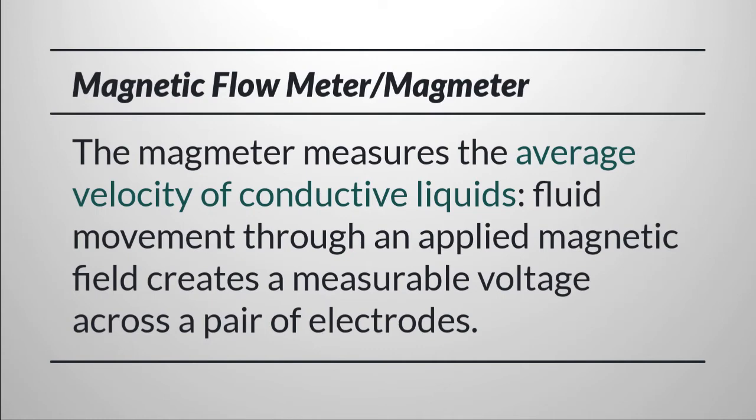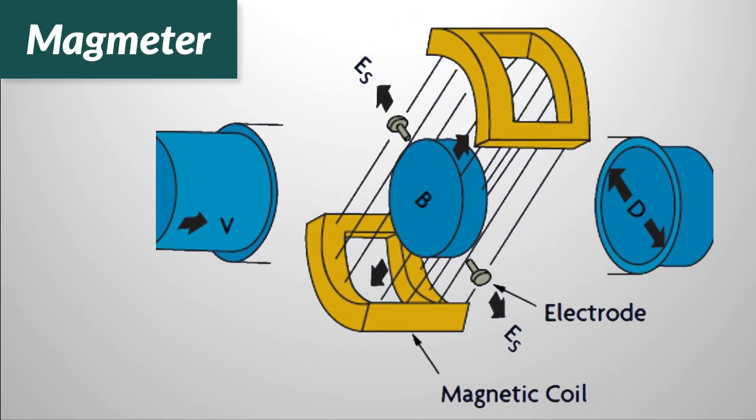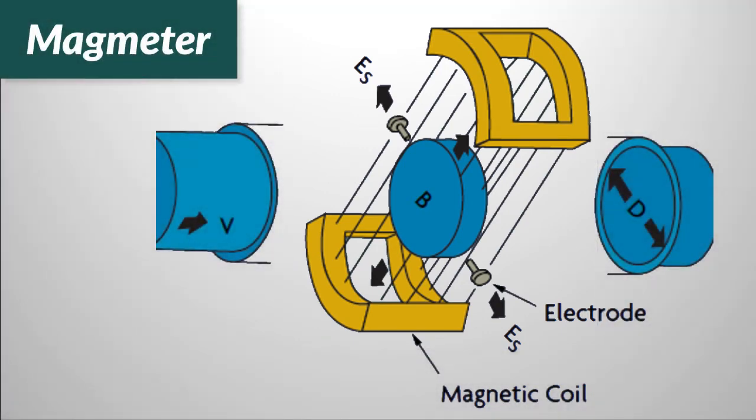The magnetic flow meter, or magmeter, works only with conductive liquids such as aqueous solutions. It consists of a non-magnetic pipe lined with an electrically insulating material. As shown here, a pair of coils generates a magnetic field and the motion of the conductive fluid through the field generates an electric potential or voltage between the electrodes proportional to the velocity of the fluid.